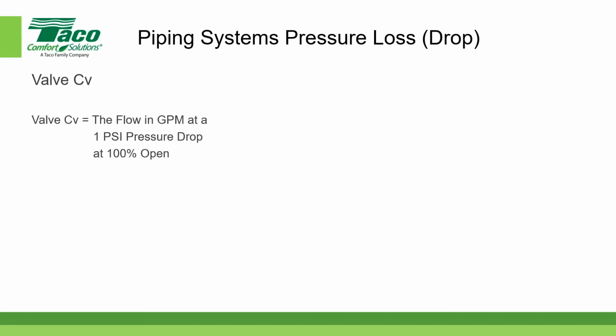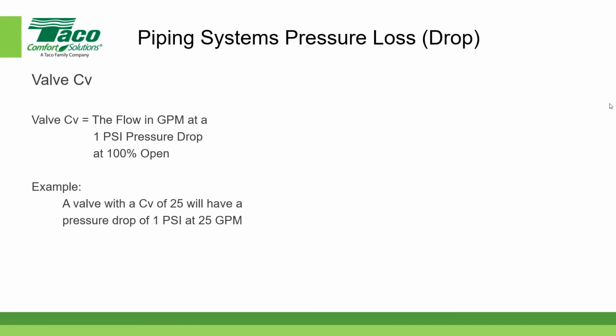Okay, so let's look at one other value that's common, called a valve CV. By definition, the valve CV is equal to the flow in gallons per minute at a 1 psi pressure drop at 100% open. So if a valve has a CV of 25, that means that at 25 gallons per minute flowing through that valve, it has a 1 pound per square inch pressure drop. Whenever you see a value for a valve, and generally speaking, most control valves have published CVs, say the CV was equal to 35.